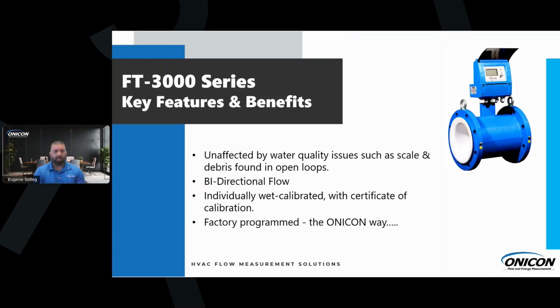Every one of our flow meters at ONICON is individually wet calibrated, with a certificate of calibration. What that means is we actually have the meter in a pipe with water flowing through the flow tube to get that calibration factor. So everything is individually wet calibrated to the highest standard. And here at ONICON, we also factory program everything to your specifications. Not everything, but most things that you can put in that order form, we will pre-program into the flow meter to your specifications.